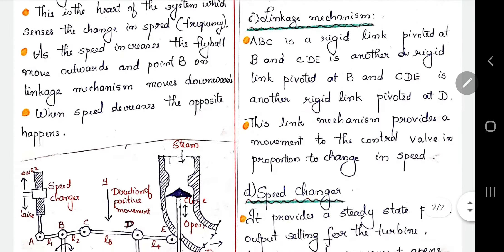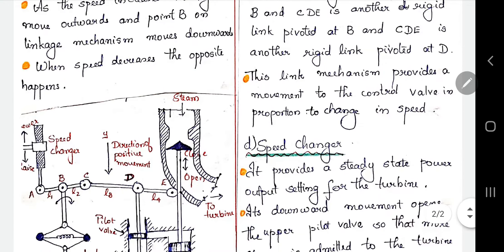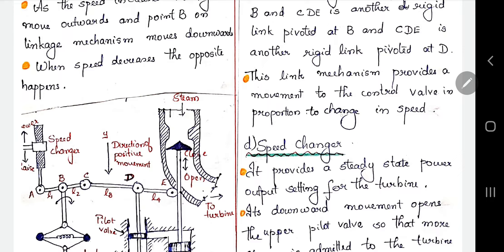The third component is the linkage mechanism. There are mainly two rigid links in the system: A-B-C is one rigid link, and C-D-E is the second rigid link. B is the main pivot of the first link, and D is the pivot of the second link C-D-E. This linkage mechanism provides movement to the control valve in proportion to the change in speed. According to the change in speed, this linkage mechanism provides movement of the control valve.